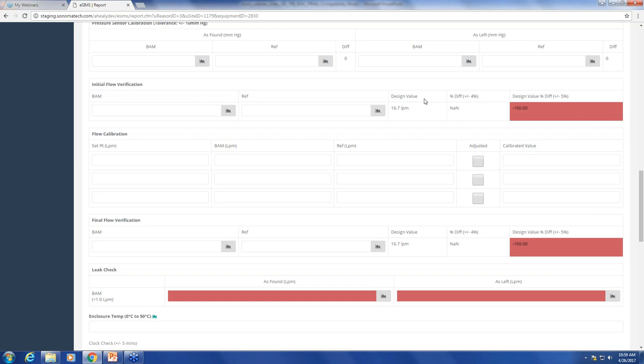For the flow verification here, of course we're going to compare against our design value and then the percent difference between the reference device. So just for kicks, let's say our BAM is reading 16.9 liters per minute and our reference device is reading 16.8 liters per minute. Our quick percent difference between the two shows we're within our threshold of plus or minus 4%, and we're within our design value threshold of plus or minus 5%.